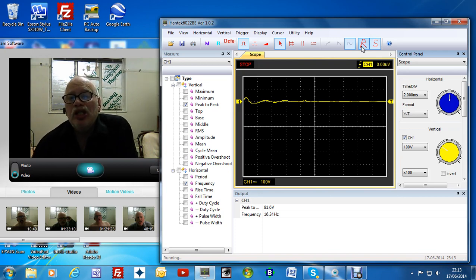Peak to peak, it's only 81 volts peak to peak, and the frequency is only 16.34 hertz. So it's actually totally different from what I thought it should be. It was calculated to be 300 hertz. It's only 16 hertz. That's probably why the voltage is much lower than it should be. Because it's calculated at 300 hertz to give you 4,000 volts, but obviously the thing doesn't work like that. But the inductance is much higher than I thought it was.